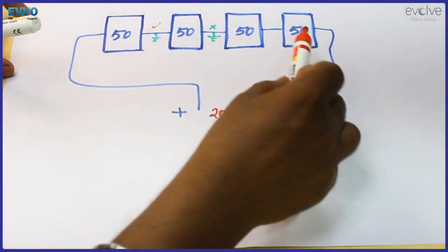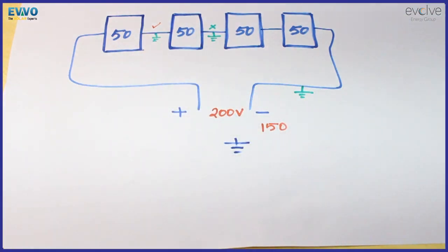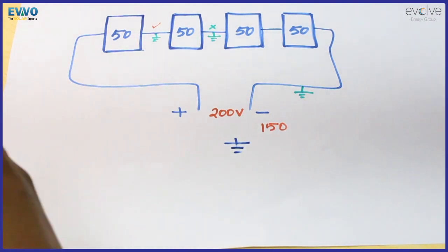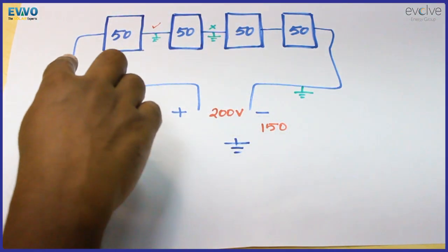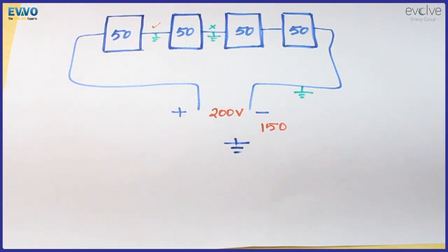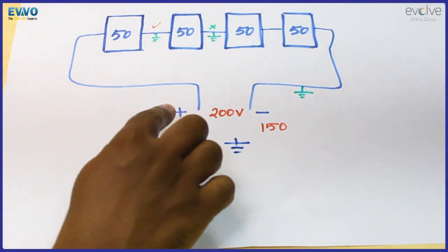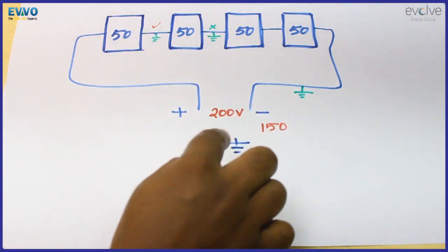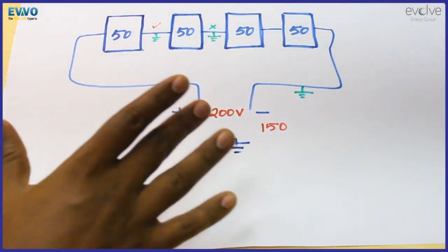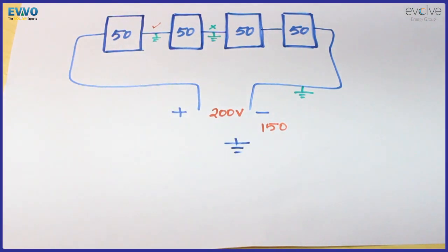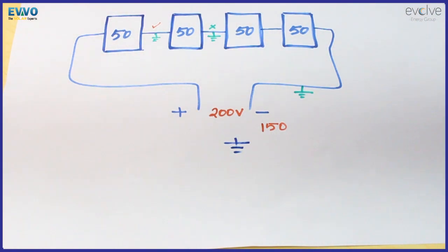This is how you identify where the leakage is happening in on-grid solar systems. In reality it's not just four solar panels — you may have 20 or more. By knowing the voltage of one single solar panel and measuring the voltage between positive to ground and negative to ground, you can easily identify where the fault is happening.